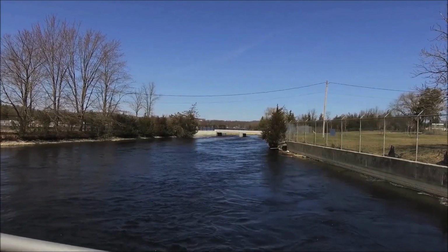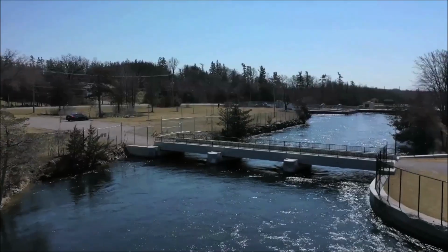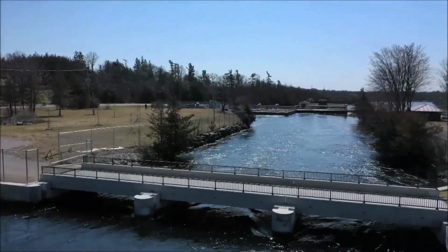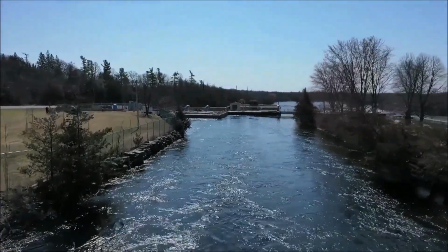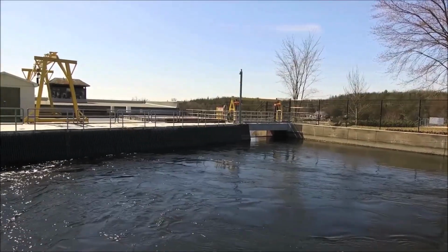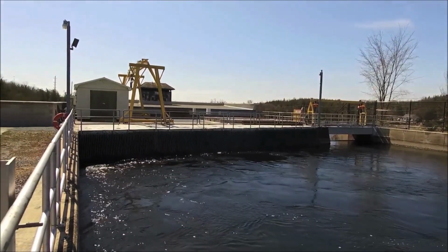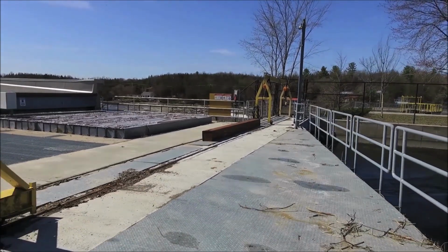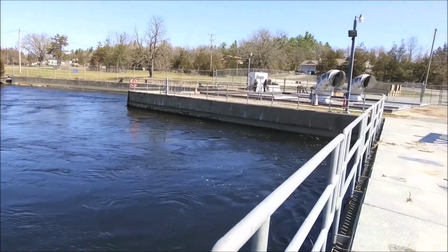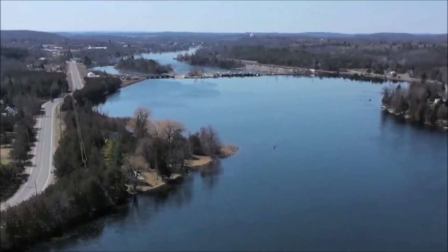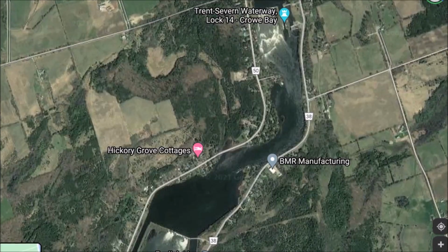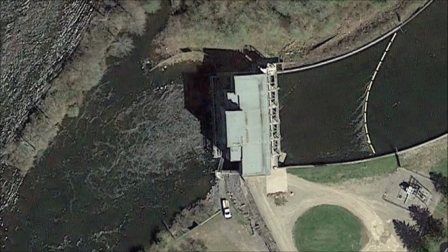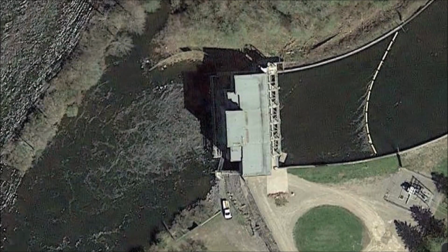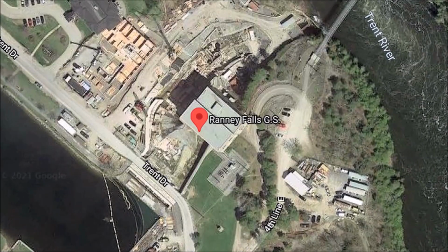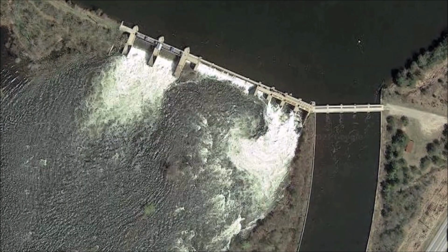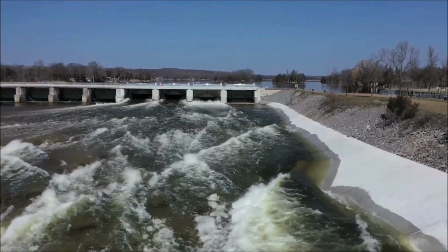The operation of the dam is also very critical with regard to the river flow. Normally, with run-of-river operation, any disruptions at the turbine are managed by opening gates up to the maximum flow. However, at the Campbellford plant, we do not have a dam structure with gates, only an ice sluice gate, which is primarily used to pass debris and ice in the winter. Given the close proximity to the next plant down the road, we have a very narrow communication bandwidth with Trent River Waterway. We must notify them immediately of any changes in load that will impact the flow. They will make the necessary changes at the dam to ensure that the water levels stay at a safe level.